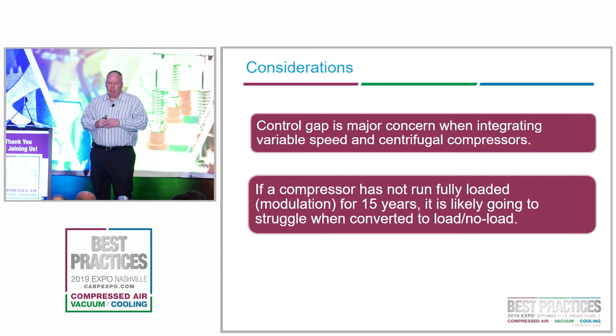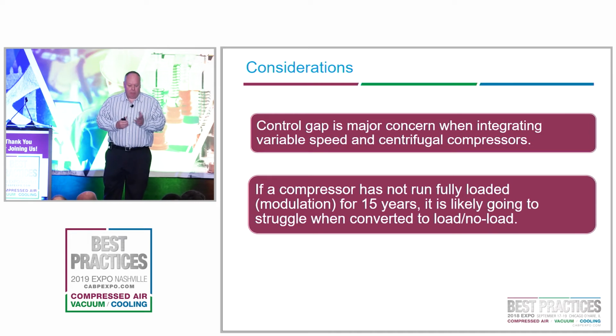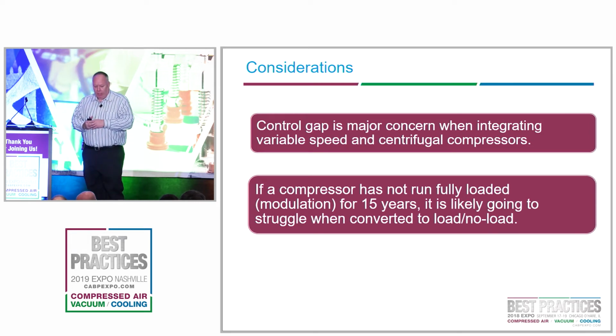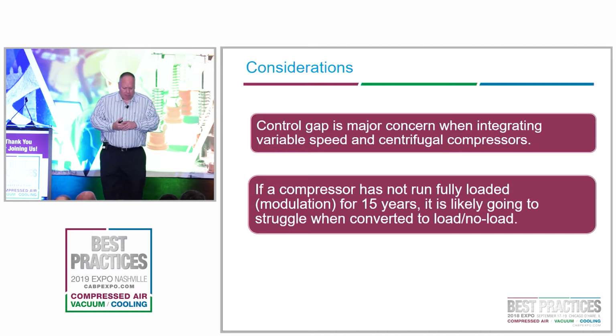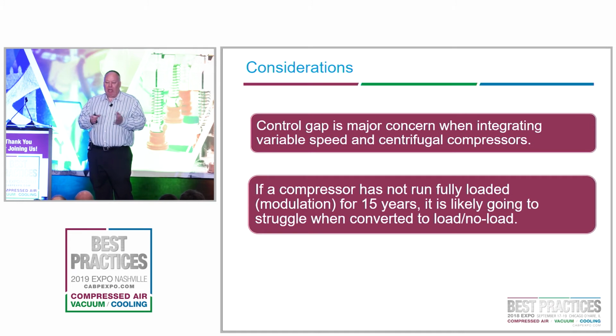Those are things that need to be looked at closely when considering a system. One of my pet peeves: you've got 4 or 5 modulating compressors that have been modulating forever, running partly loaded. Then you put in a control system and decide to turn off 2 of them to make the other 3 run fully loaded. It works for a couple hours until they trip on high amps, high temperature, or something, because they haven't been maintained in a way that allows them to run fully loaded.